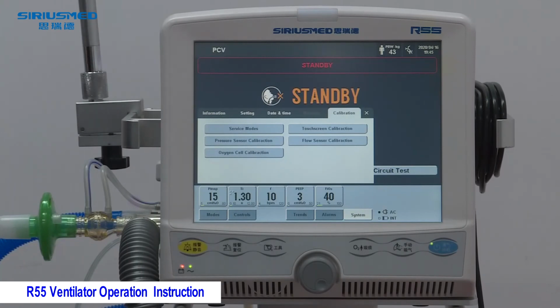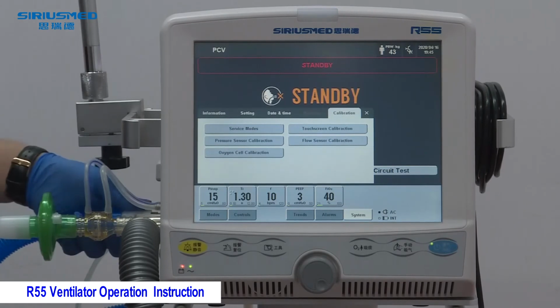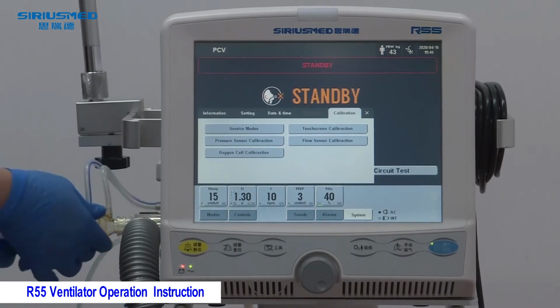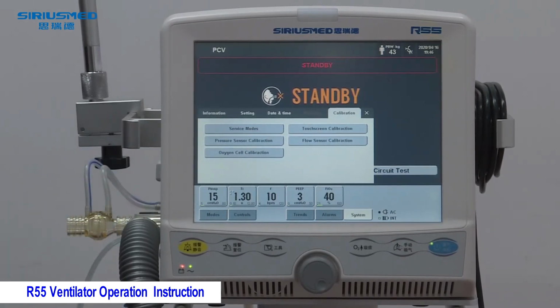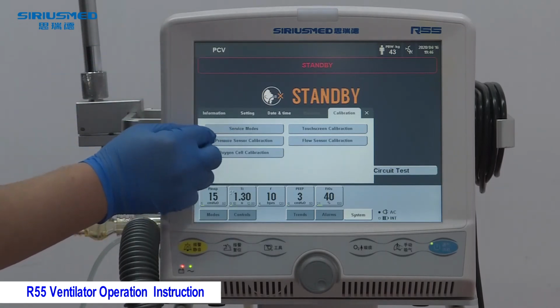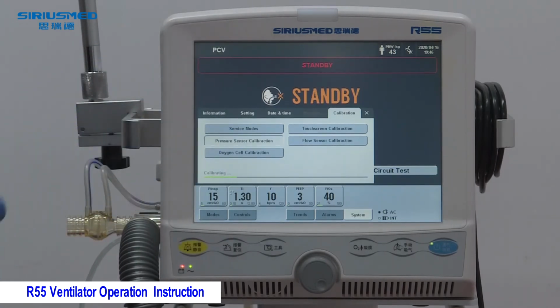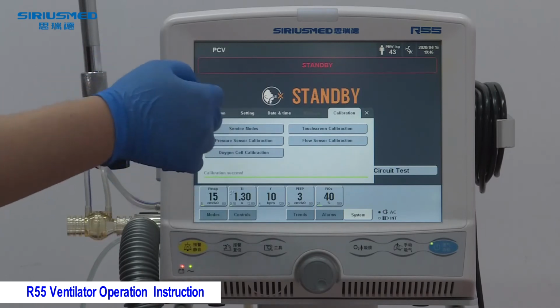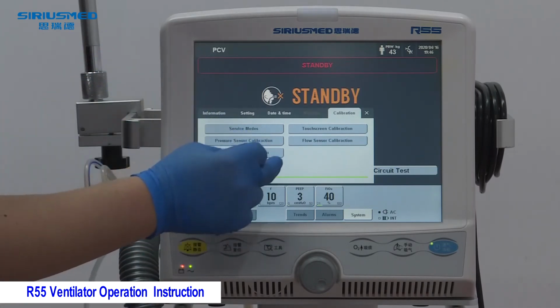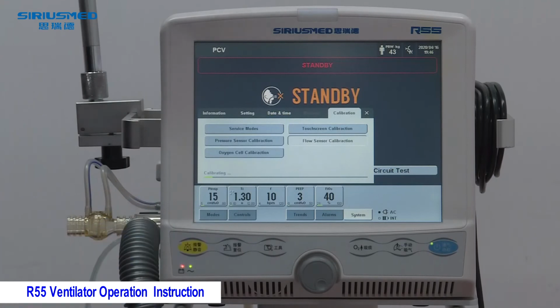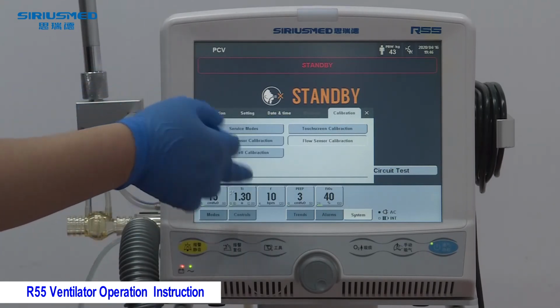To do this calibration, firstly, we need to take off the tubes and make sure there's no flow directed to the sensors. And then we click the pressure sensor calibration. It will be done by itself. Also, it's similar: click flow sensor calibration. Also, it will be done by itself.